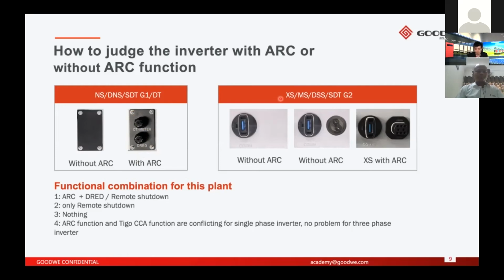And also for some of our new products like XS, MS, DSS, SDT G2, if the port on your inverter is black, it's without arc, and if it has only 2 pins, it's also without arc. But if your inverter has a communication port like this, that means it already integrates the arc function, the export power limit function. So firstly, if you want to do the export power limit function, you need to order the specific inverters from GoodWe.